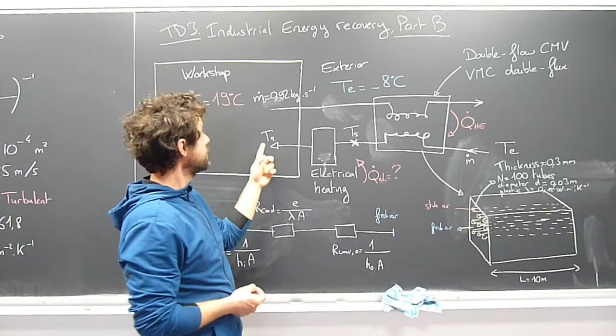We will call this TF. Because we don't have full heat recovery in this heat exchanger, we need to add a supply of electrical heating to heat the air up to the workshop temperature TA. So the idea is, with a given design of heat exchanger, to first calculate the overall heat transfer coefficient in order to estimate the heat flux exchanged, and from that calculate the intermediate temperature and how much additional heat supply we need from the electrical heating.